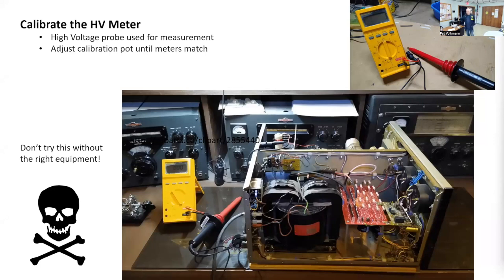You have to make these adjustments basically with the interlock defeated and the cover off, and this is a 3600 volt supply. So don't do this if you do not have the right equipment. The right equipment is a high voltage probe and one hand behind your back while you're making the measurements. And at that, you don't adjust the power supply while measuring. You make the measurement, you turn everything off, you make sure the capacitors are discharged, you adjust the potentiometer, you turn it on, let it come back up, and measure the voltage.